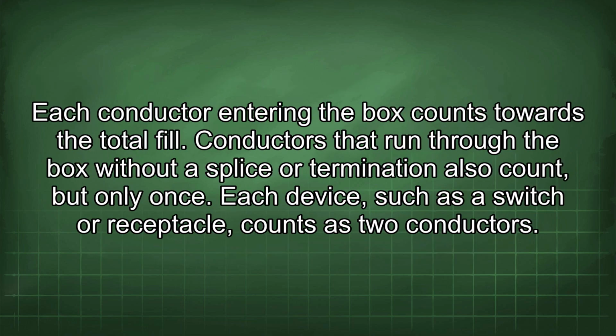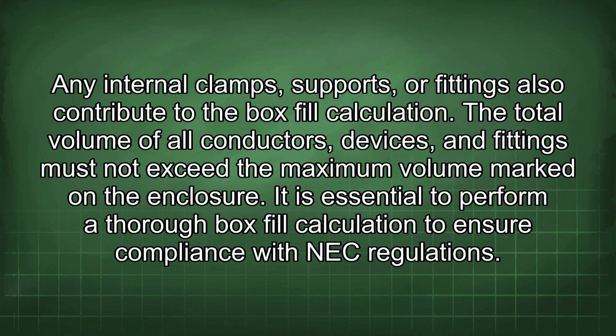Each conductor entering the box counts towards the total fill. Conductors that run through the box without a splice or termination also count, but only once. Each device, such as the switch or receptacle, counts as 2 conductors. Any internal clamps, supports, or fittings also contribute to the box fill calculation. The total volume of all conductors, devices, and fittings must not exceed the maximum volume marked in the enclosure. It is essential to perform a thorough box fill calculation to ensure compliance with NEC regulations.